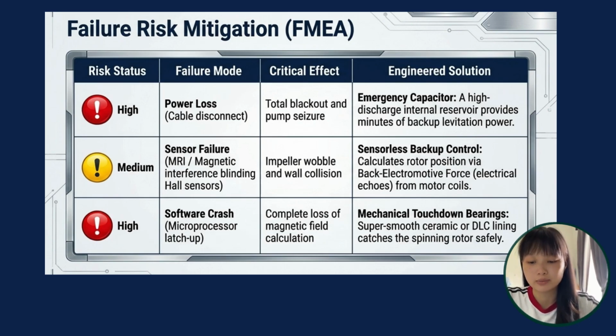So the first problem is sudden power loss. Magnetic levitation requires continuous electricity in order to keep the impeller floating. If the external power is accidentally disconnected or the batteries fail, the magnetic field will collapse immediately. The spinning impeller will lose its position and crash into the internal walls of the pump, causing a seizure and potentially damaging the blood through extreme friction. Therefore, we need an emergency capacitor or a secondary battery. This acts like a mini power reservoir that provides enough energy to keep the impeller levitated for a few minutes, which is long enough for the patient to swap batteries or plug into a wall outlet.